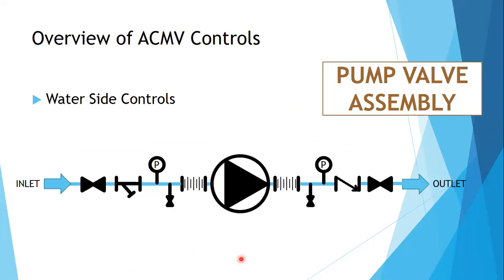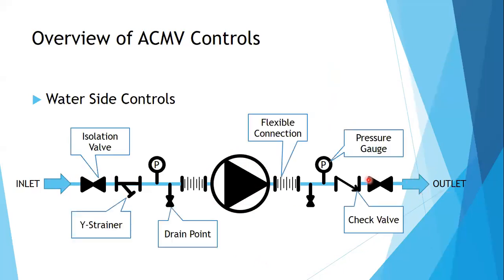Okay. Earlier, we were talking about the air handling unit and the fan coil unit valve assembly. Now this is the valve assembly for your pump. So this is the symbol of the pump. So inlet, outlet. Again, isolation valve to isolate your pump. So anything that happens to the pump, you can dismantle the pump, close the isolation valve, your system is still working fine. Your system can still work without one of the pumps. You can do all your maintenance and your installation works or repair works as needed.